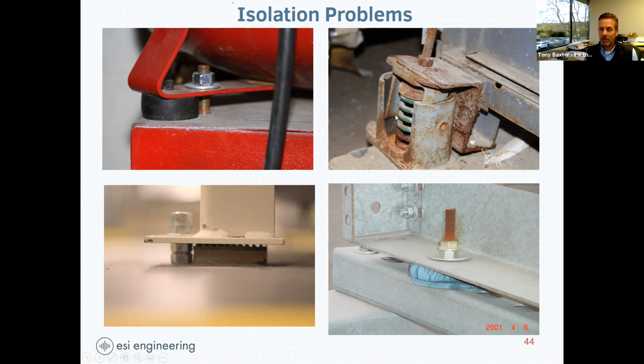We're not fans of this type of restrained isolator anyway, where the two halves nest inside each other—they invariably get bound up. You see this especially under fans on rooftops, where snow and ice, and sun beating down on the rubber in summer, cause it to rust, and it invariably stops working.